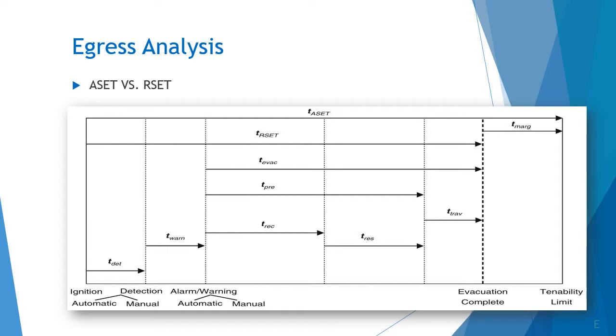detector. However, if you don't actually have an active alarm or water suppression system in place, that time to detection is someone's nose. So how long is it going to take for someone to physically react to and smell smoke? The human nose is actually very sensitive, and a lot of times it can beat the smoke detector, provided someone is located within the vicinity of the fire. So your time of warning is the actual time that your alarm system is going to go off.